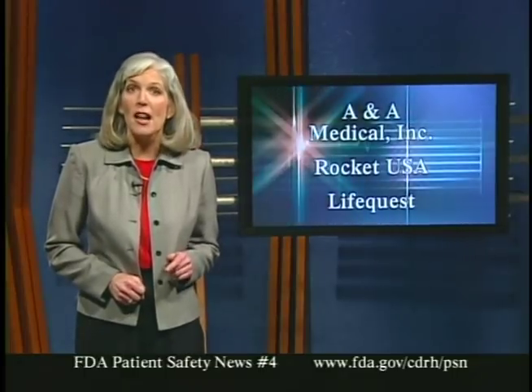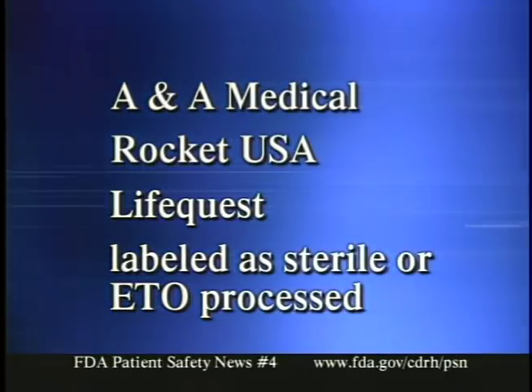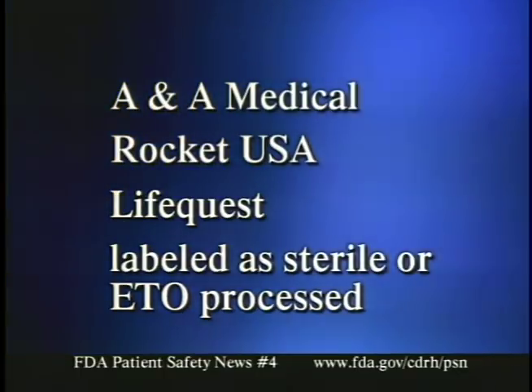Here's more on a breaking story from our last broadcast: an urgent recall of certain medical devices manufactured by A & A Medical, Inc. of Alpharetta, Georgia. This company also does business under the names Rocket USA and LifeQuest, and it manufactures many types of OB-GYN and surgical devices. The reason for the recall is that devices labeled as sterile or ethylene oxide processed actually may not have been sterilized. As a result, using these devices could cause serious and possibly life-threatening infections. This recall includes all products manufactured under the names A & A, Rocket USA, and LifeQuest that are labeled as sterile or ethylene oxide processed.